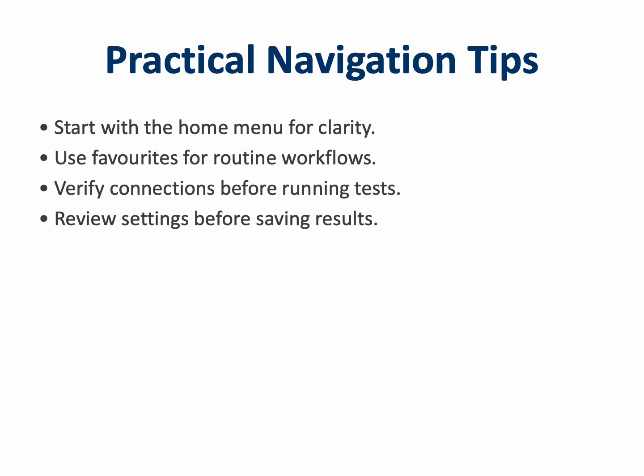Efficient use of the Rigel 288 Plus comes down to habit and consistency. Always start from the home screen to maintain orientation. From there, navigate to your required tests using arrow and soft keys. For recurring maintenance, add frequently used sequences to your favorites list. This saves valuable time during rounds. Before pressing run test, verify that your test leads and connections are correct. Once the test completes, take a few seconds to review and confirm the on-screen results before saving or printing. These small habits reduce errors, improve data integrity, and help maintain smooth, repeatable operations in the field.